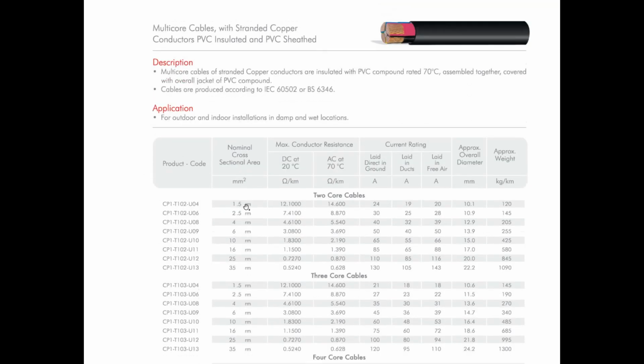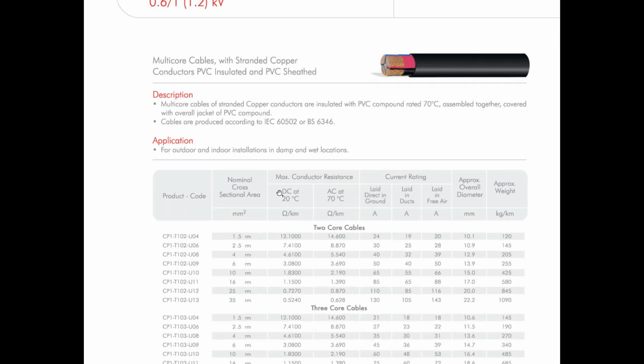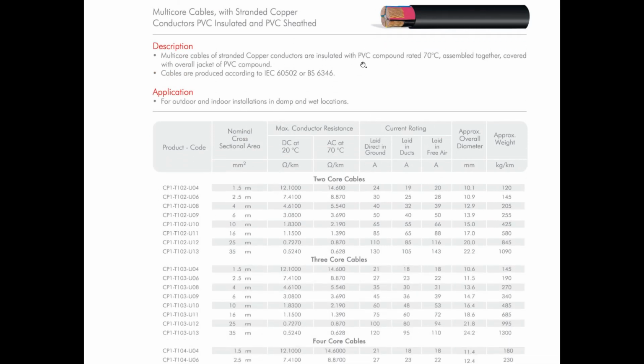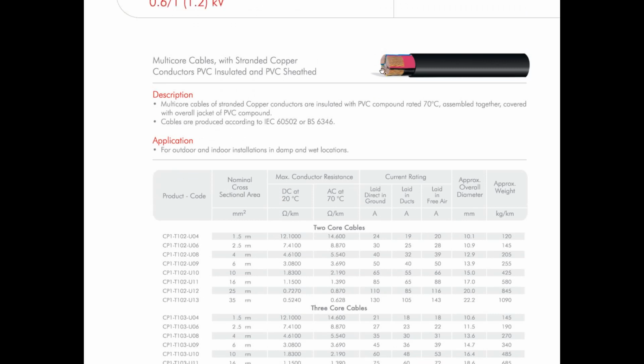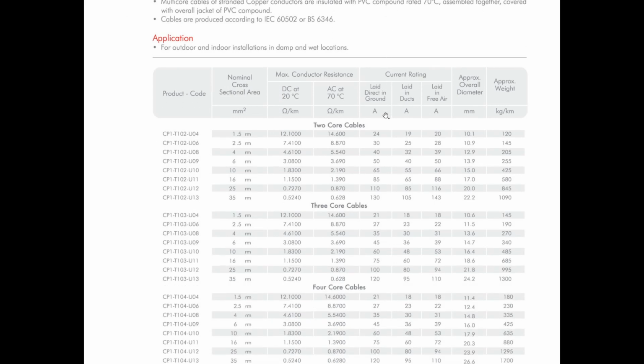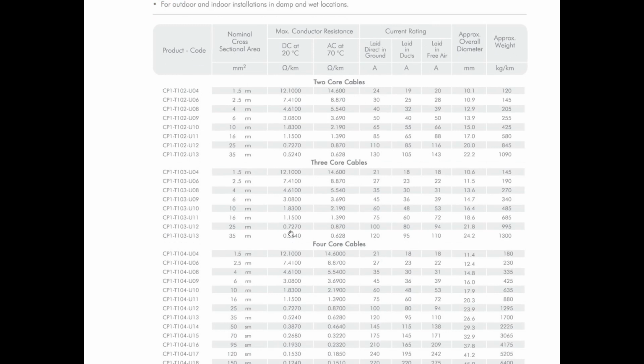As you can see here, the voltage is the same as we need, and the PVC insulation which we have selected. And it has 1, 2, 3, 4 cores: the three phases and the neutral. So let's go down here. You can find here four-core cables, all of these are four-core cables. This is the nominal cross-sectional area in square millimeters, which we need. Neglect the resistances now. This is the one which is important for us: the current rating.